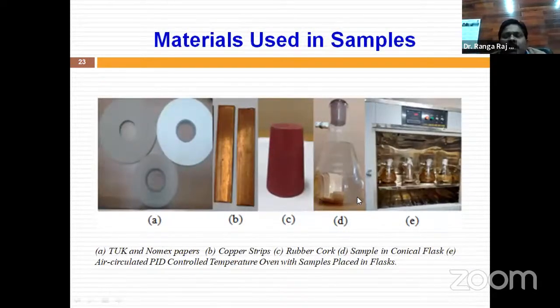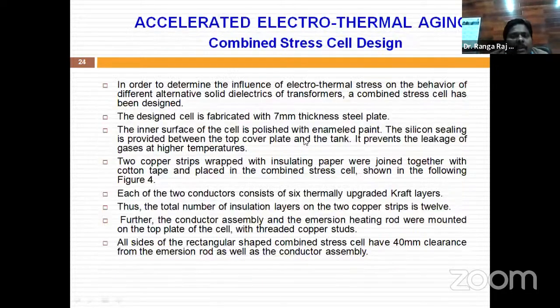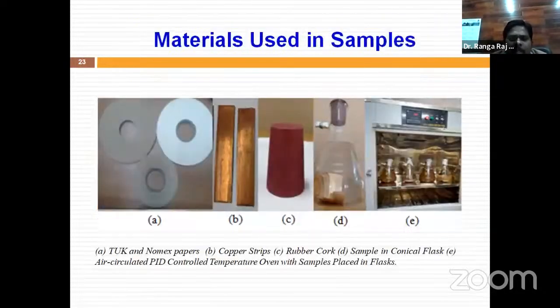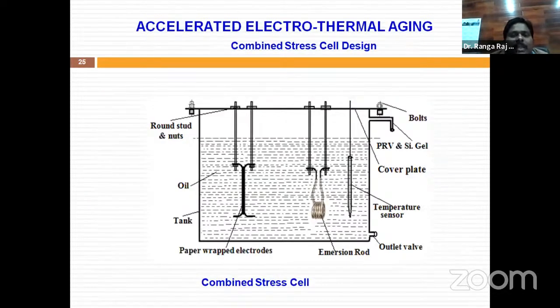So we increase the temperature and fix the time according to the standards, collect the samples properly, and seal them properly using these rubber corks. Perform all the tests we discussed and note down the readings at 120, 160 degree points. Make the graph. For fresh oil you know the value, and for aged samples you can note down the deviations.